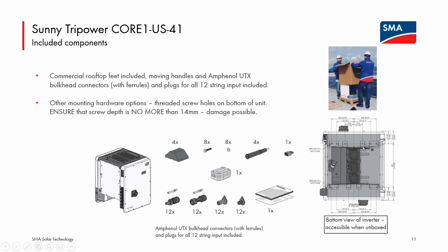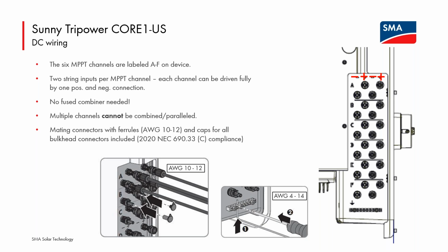And this picture shows a little better the construction of the fan tray. So there are 3 fans in that tray. There's a handle to release it and drop it for inspection for PM check. So pretty straightforward setup. We're aiming to have it where it's very easy to get the inverter close to a final location, unbox it, use the moving handles to put it in final location, lock it down, and then wire it up. So again, we're aiming for a very easy to install unit.